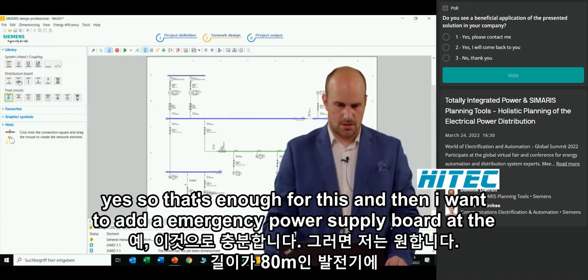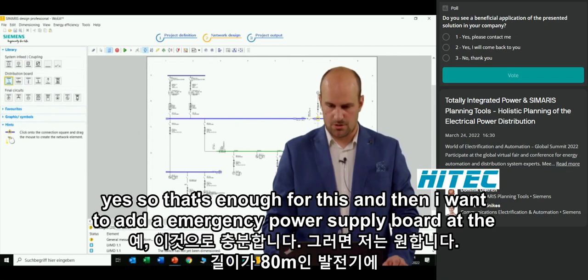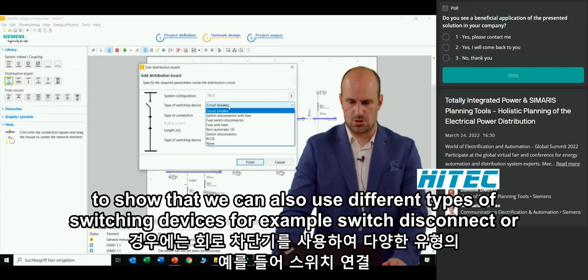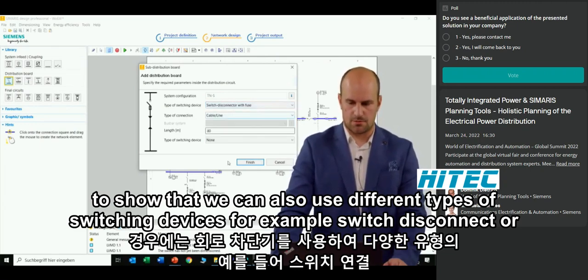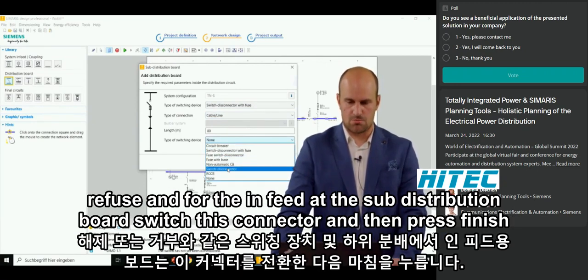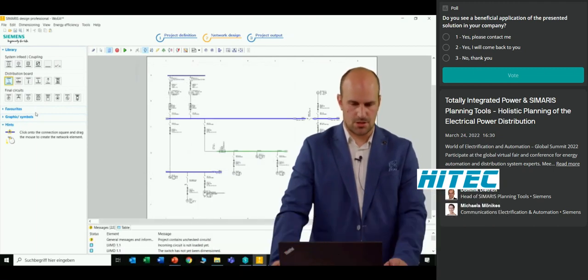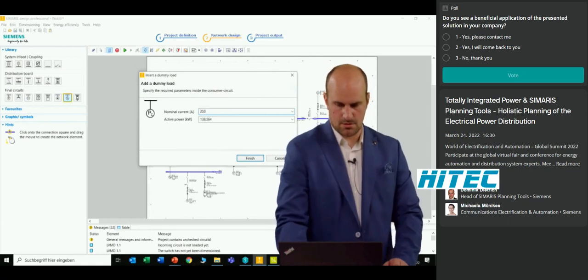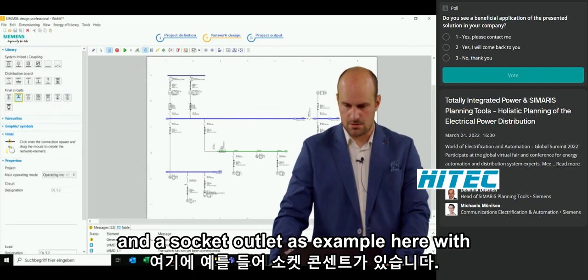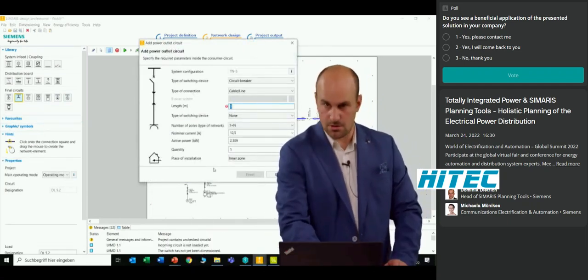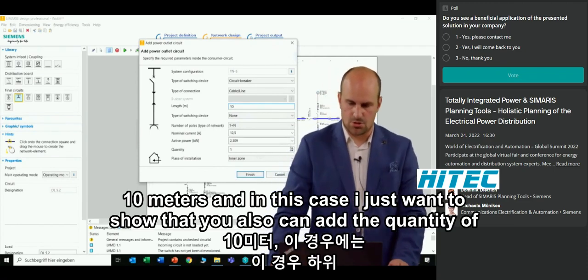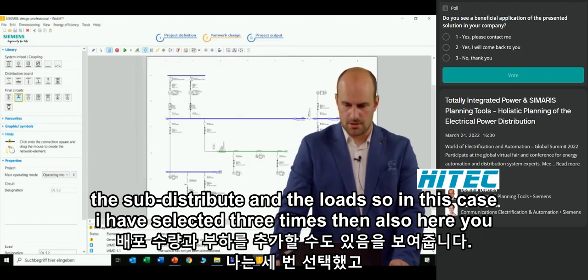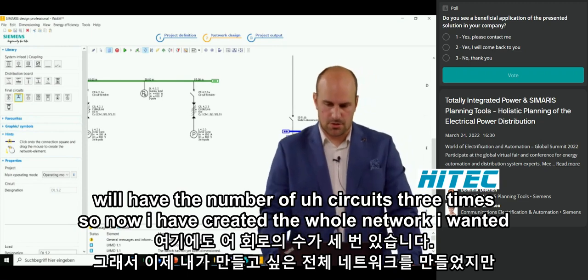I also add an emergency power supply board at the generator, with a cable length of 80 meters. In this case, I use different switching devices — a switch disconnector with fuse and, for the in-feed at the sub-distribution board, a switch disconnector — then press finish. We add a dummy load for all connected loads with 250 amps, and a socket outlet with 10 meters. I also show that you can specify the quantity of loads — in this case, three times — so the network will have three circuits.